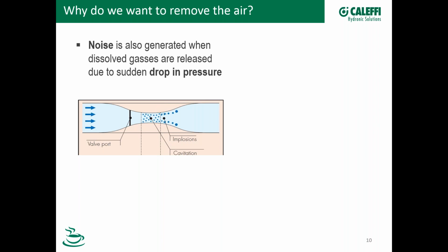And pressure is inversely proportional to velocity. So as the velocity goes up, the pressure goes down. And if the pressure at this small cross-sectional area falls below the vapor pressure of the fluid, then microbubbles will form from the dissolved air. And then when the cross-sectional area increases as we exit the valve, these microbubbles will implode and go back into solution, and that's called cavitation. So besides causing noise, cavitation causes serious damage to the piping walls and to everything else in its path.